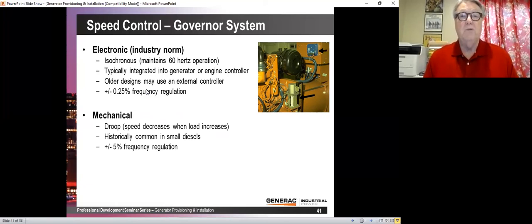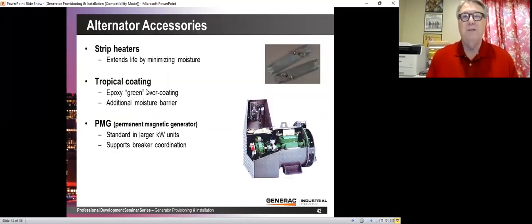Governors typically are electronic these days, and they will keep your frequency within 0.25%, and that is pretty standard. Strip heaters, we generally feel, are not necessary in this area because it's got non-hygroscopic insulation in the alternator, and we just don't see problems with moisture on these standby generators, particularly because the engine has some heat going into it. It's right there by the alternator, and all you need is just a little bit of temperature above ambient to keep any condensation from occurring.